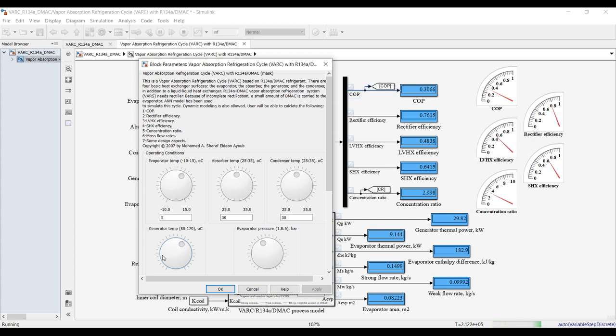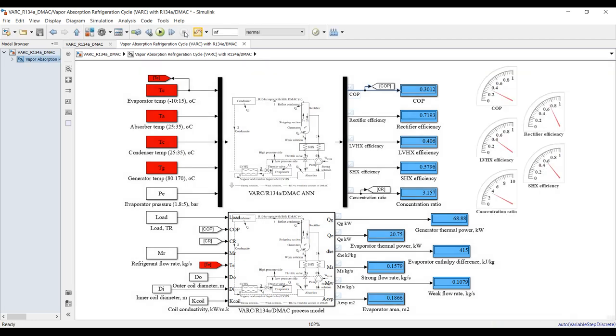COP is increasing as I raise generator temperature. Now let's decrease it back, then increase the refrigerant load. Increasing the load has a massive effect on evaporator area, thermal power, and strong/weak mass flow difference. Stop the simulation. This dynamic mode is very useful for recognizing which parameters have a direct effect on outputs.